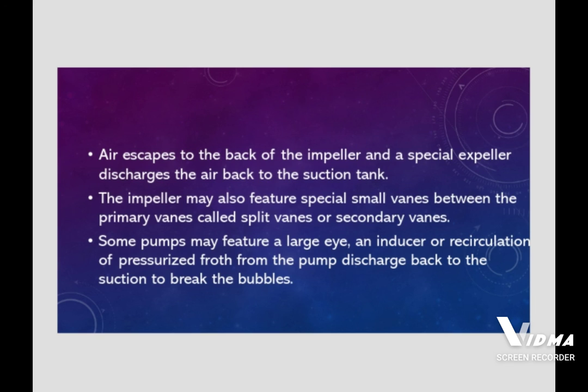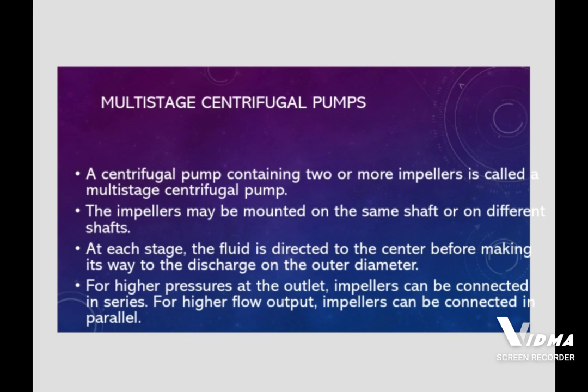A centrifugal pump containing two or more impellers is called a multi-stage centrifugal pump. The impellers may be mounted on the same shaft or on different shafts. At each stage, the fluid is directed to the center before making its way to the discharge on the outer diameter. For higher pressure at the outlet, impellers can be connected in series; for higher flow rate output, impellers can also be connected in parallel.